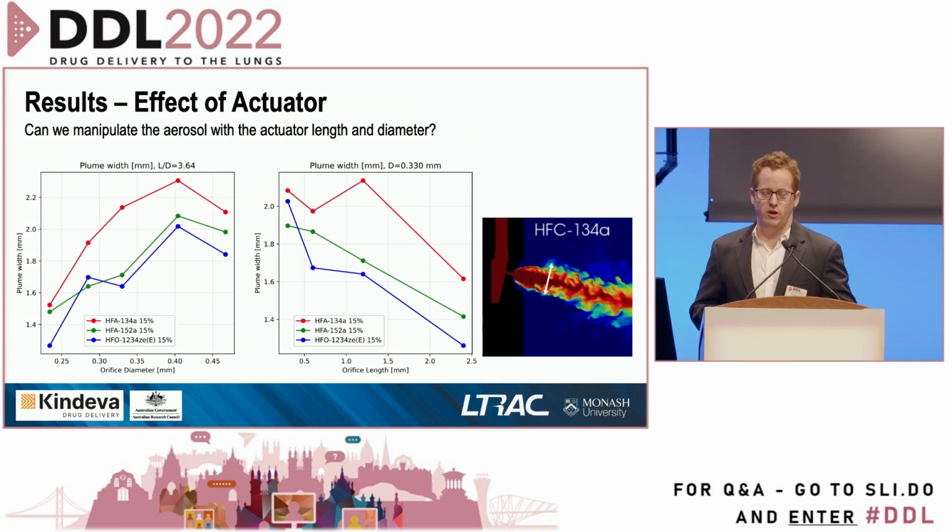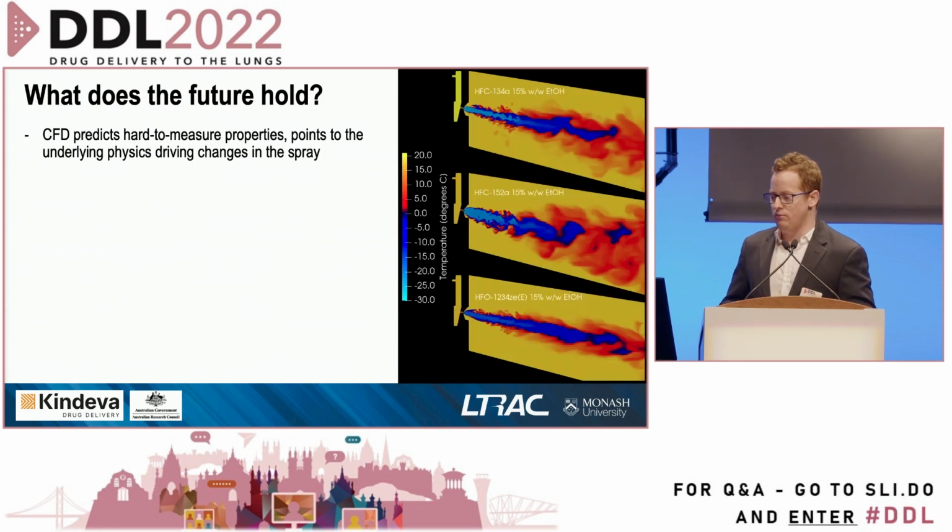This is promising. This suggests that redesigning the actuator orifice means you can tune it to get equivalence if you want, or to hit a particular value.